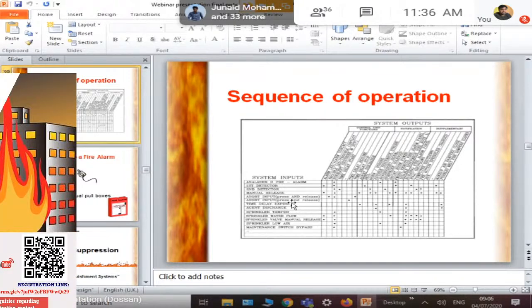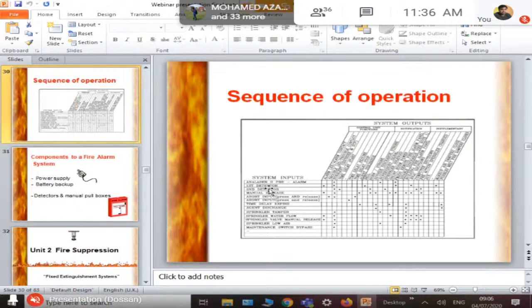So it's like this. Say you have a smoke detector being identified. So where does the signal go? The first dot shows that it goes to the fire alarm panel. Okay. The second dot, if you see, is to the next output device. But we will be giving input to the notification devices when there is a fire. This is how it works.